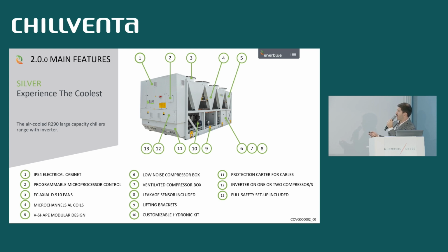The hydronic module can be customized in the sense that we can choose to equip the unit with 1 pump, 2 pumps, inverter-driven pumps, water tank, and so on. The part below the electrical cabinet is an enclosure to protect the electrical cable, so the power supply which goes into the unit from below. The inverters placed here are under the unit. It is possible to decide, so without inverter or with inverter, and the unit is, as mentioned, thought to prevent any risks concerning the flammable refrigerant.